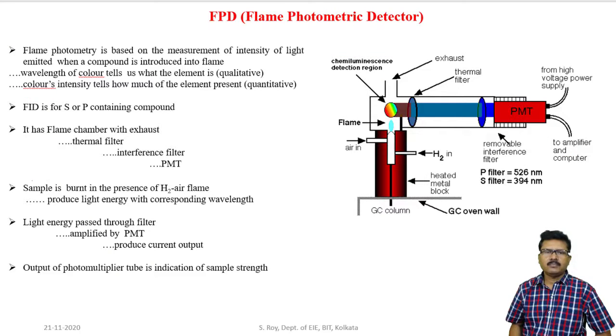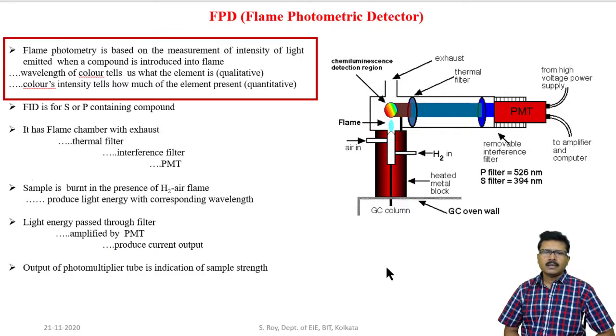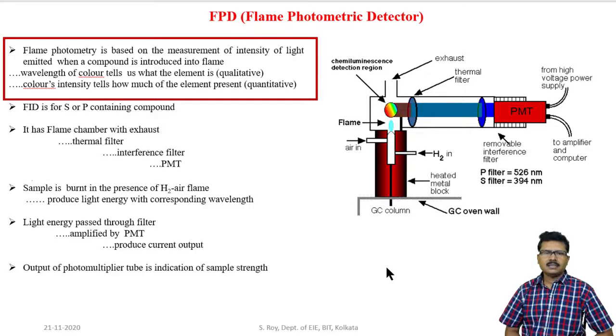Now explaining flame photometric detector. Flame photometry is based on the measurement of intensity of light emitted when a compound is introduced into the flame. This gives qualitative as well as quantitative measures. The wavelength of the color tells us what the element is — this is qualitative. The color intensity tells us how much of the element is present — this is quantitative.